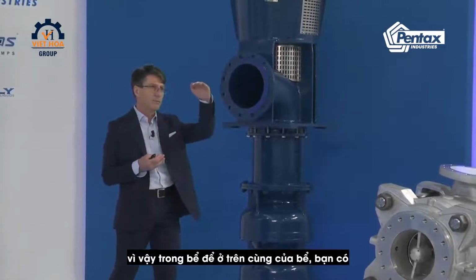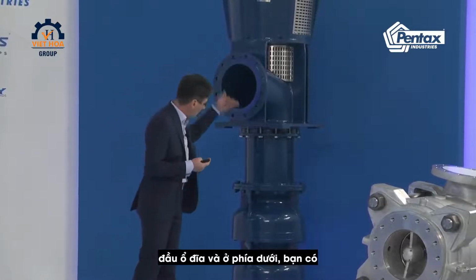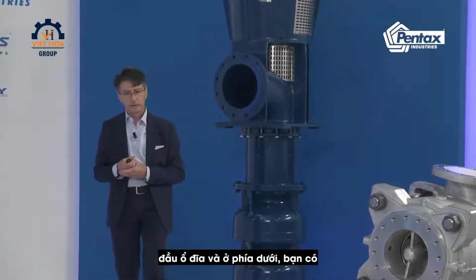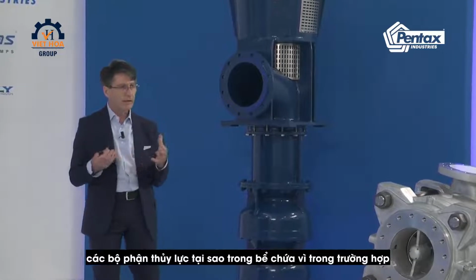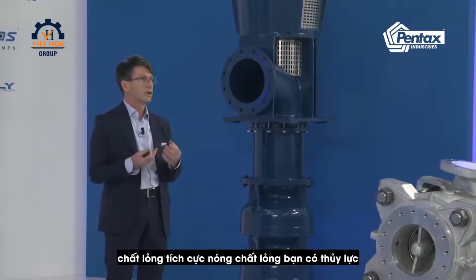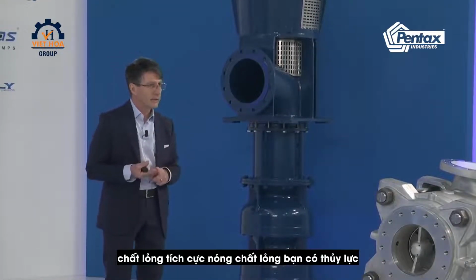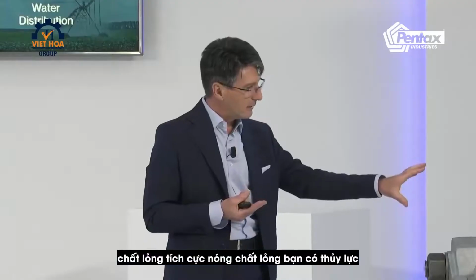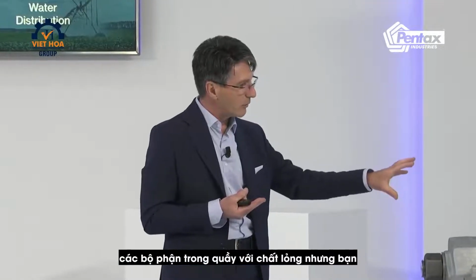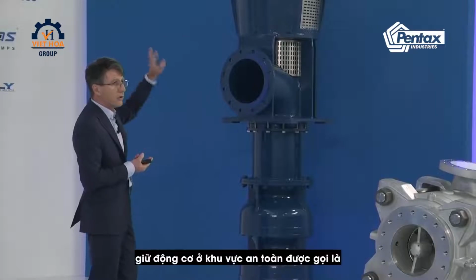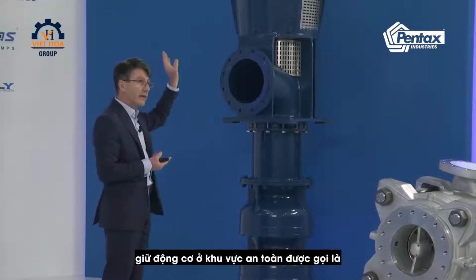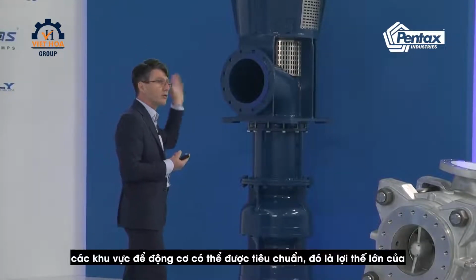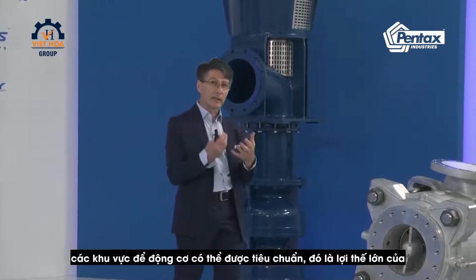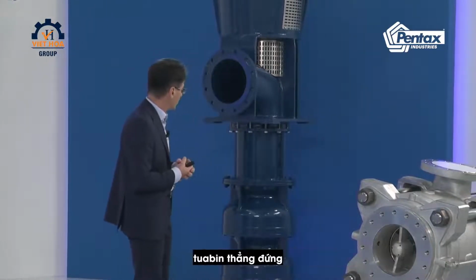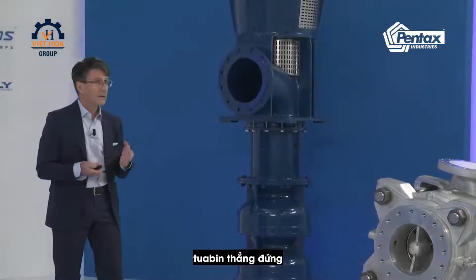So at the top of the tank you have the drive head, and on the bottom you have the hydraulic parts. Why in the tank? Because in case of hot liquid, aggressive liquid, you have the hydraulic parts in contact with the liquid, but you keep the motor in a safe area, non-hazardous area. So the motor can be standard. So that is the great advantage of the vertical turbine.